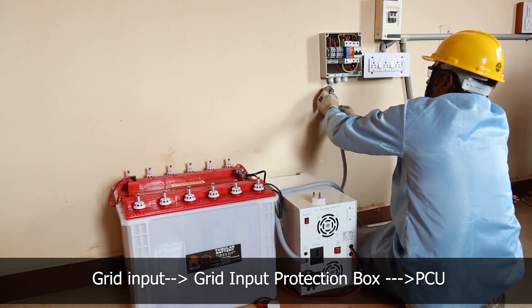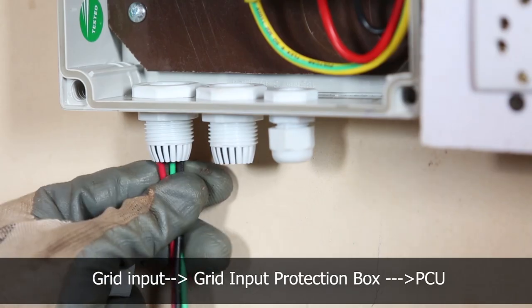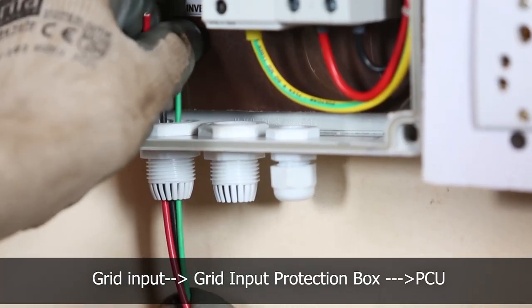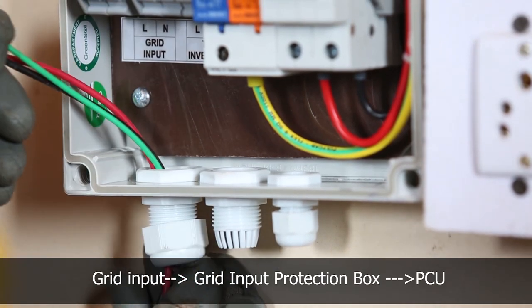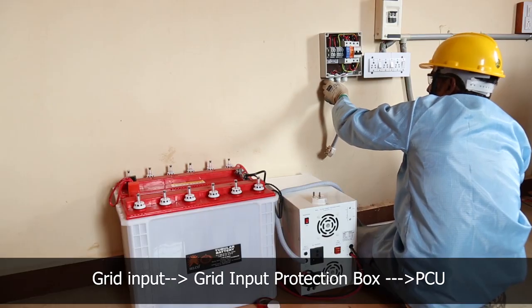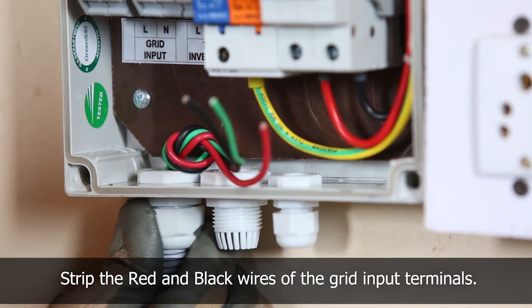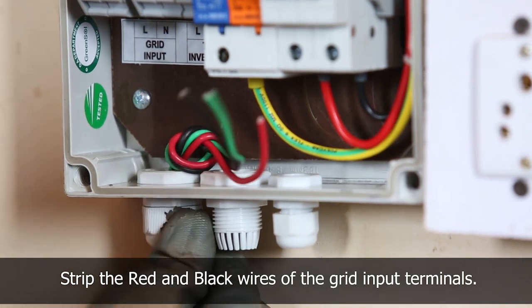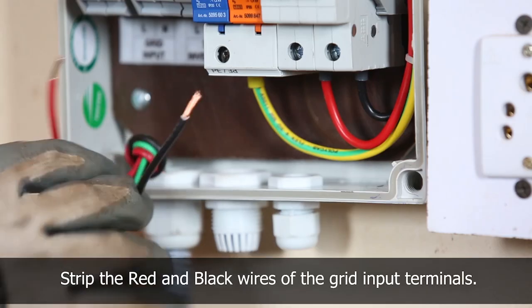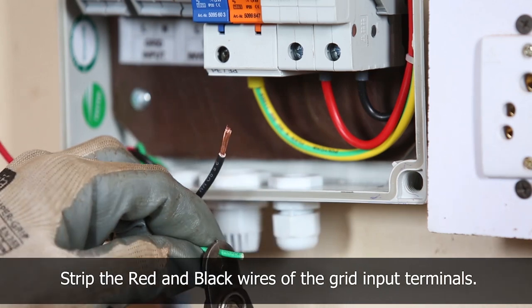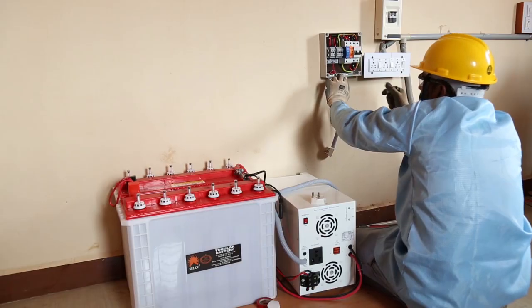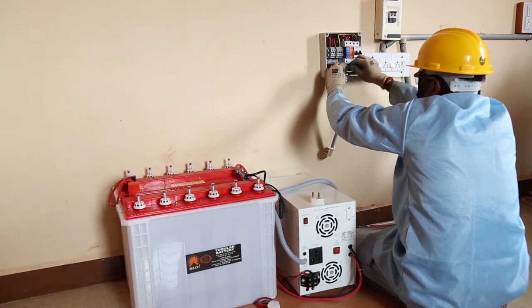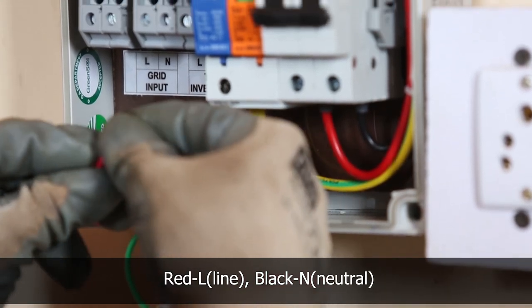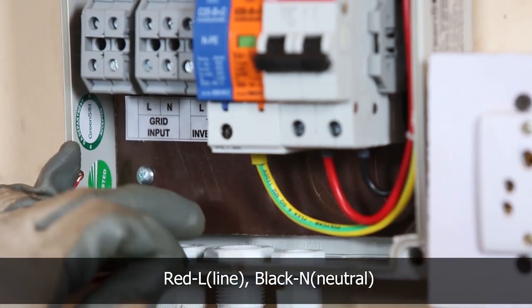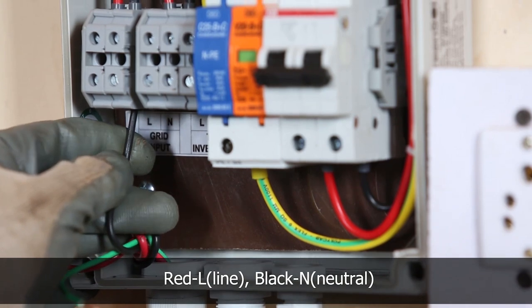Connect the grid to the input terminal of grid protection box and the output of the grid protection box to the power conditioning unit. Strip red and black wires. Connect it to the input terminal of grid input protection box. Red wire is connected to the line terminal and the black wire is connected to the neutral terminal.